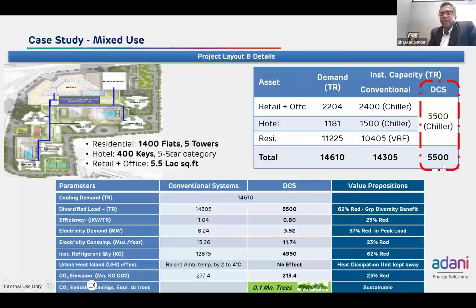So during the day, because of the complementarity of use, the same capacity which serves the retail and office and other establishments feeds the residential during the evening. So with that, we have been able to get a 62% reduction in the total capacity which we are installing.